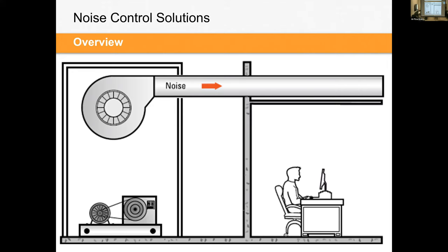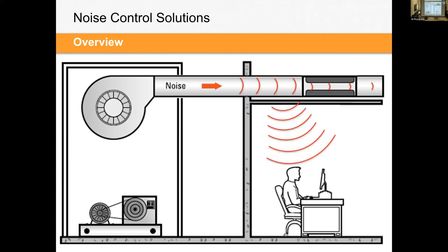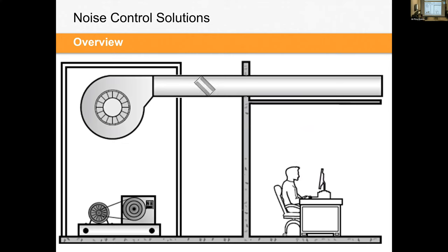So in general, installing a silencer in this duct system could be a great option. Silencers are great at attenuating the noise, through the magic of PowerPoint animation. You can see that sound wave. It's pretty impressive. I spent a lot of time making these slides. And you can see as that sound energy approaches the silencer, a lot of that energy is dissipated and absorbed in those baffles and is now quieter downstream of that silencer. Unfortunately, the placement of the silencer in this circumstance wouldn't really yield a direct benefit for that breakout noise. Moving the silencer closer to the fan, maybe inside of the mechanical room, would really help to achieve optimal insertion loss, but also address that breakout noise concern.